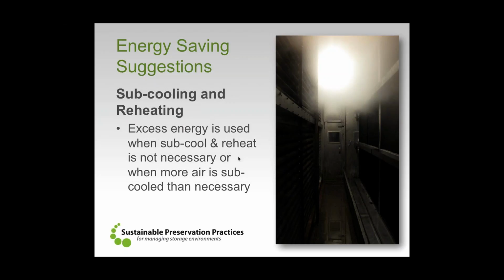Subcooling and reheating, that process we've talked about in the past, is where we subcool the air at the cooling coil in order to achieve the dew point that we need. And then we reheat it in order to achieve the proper supply air temperature condition, as well as the appropriate relative humidity to go into the space.